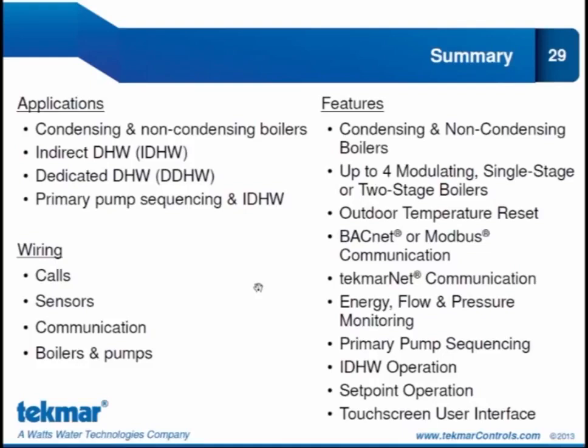The features that we covered included 10 new features to the 284. In particular, we wanted to look at how it can control the mixed heating plant, how it treats condensing and non-condensing boilers differently, how we can wire and control up to 4 modulating, single-stage or 2-stage boilers. We looked at outdoor temperature reset as one of the possible application modes, and the 4 other application modes. If that wasn't the type of system we had, we can configure it to operate for a fixed set point, for dedicated domestic hot water, or to receive input from an energy management system or a building automation system.